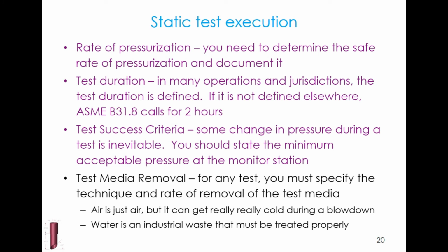Then you've got to talk about test media removal. For any test, you have to specify the technique and rate of removal of the test media. Air is just air, but it can get really cold during a blowdown.